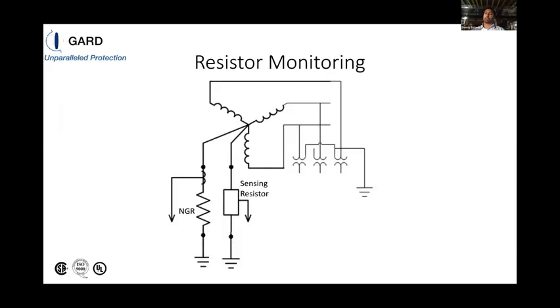The way that we do the resistor monitoring is a bit different in comparison to the competitors in the market. The way that we do this is that we're applying a sensing resistor between the XO point and ground, as well as a CT that's located to detect how much current's flowing through the neutral. Our sensing resistor also gives us a reference voltage for what's happening at the XO point. Now, if there's 0 volts and 0 current, we still have to monitor this neutral grounding resistor for open and short circuit scenarios.